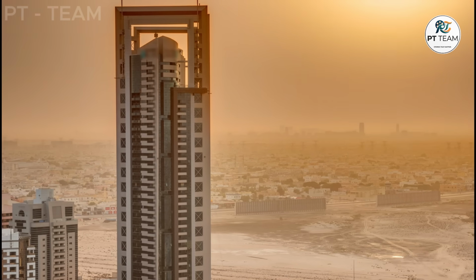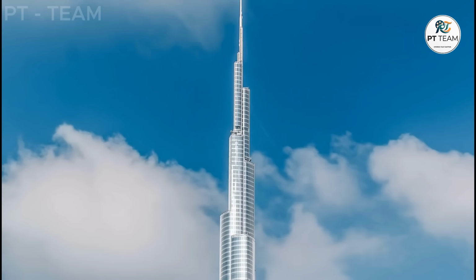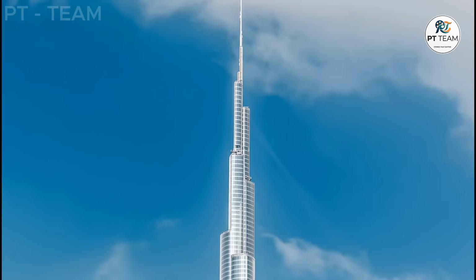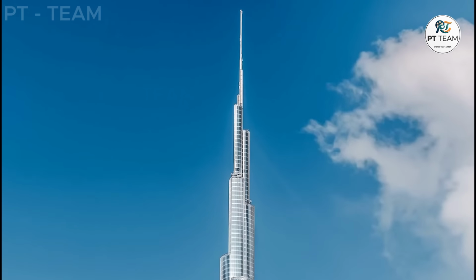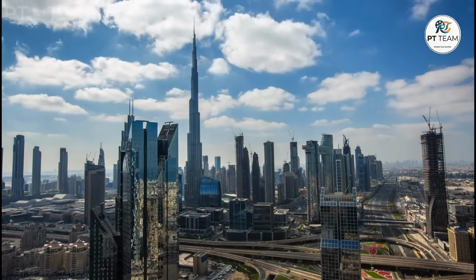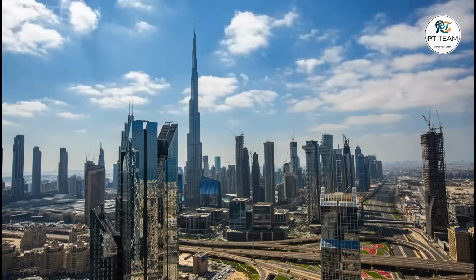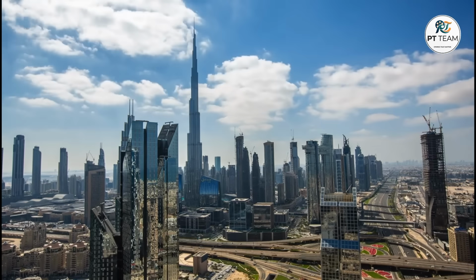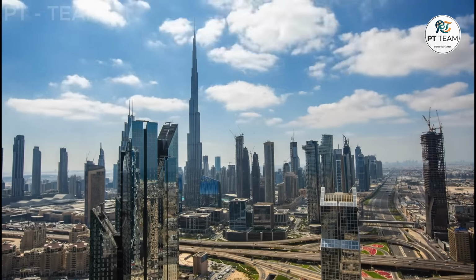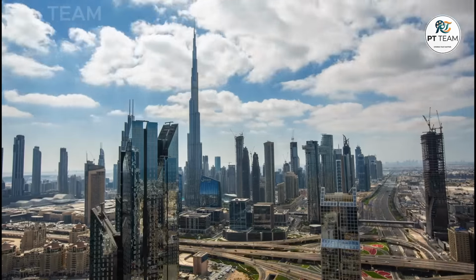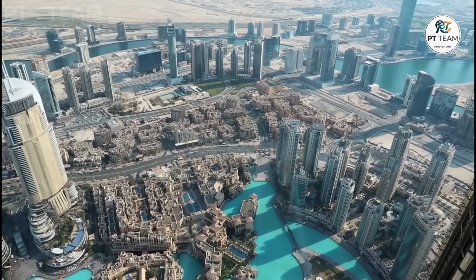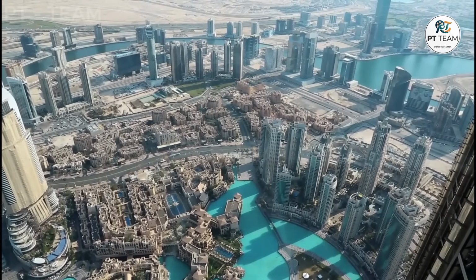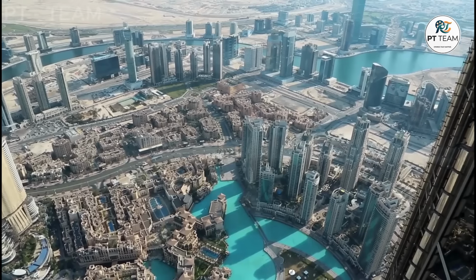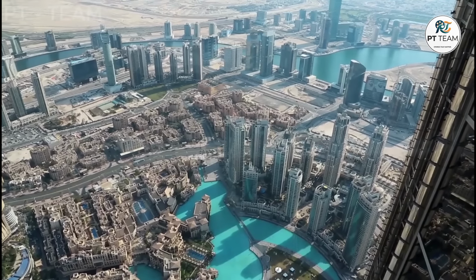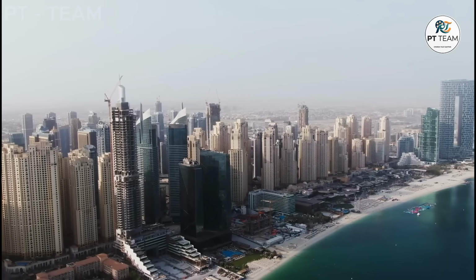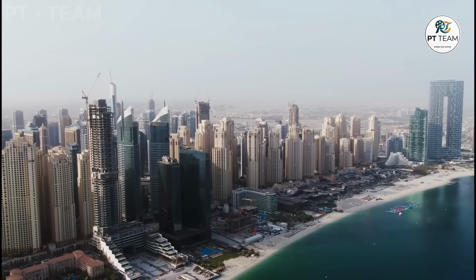But all of these technological advancements come with a strict conditional reality. Sensors do not physically replace clogged filters. Software cannot climb into a dark duct and repair a broken rubber seal. Data is entirely useless if the management team does not have the budget to deploy human labor to fix the problem. None of these innovations eliminate the fundamental need for continuous physical maintenance. Dubai can absolutely keep the desert outside its luxury towers, but it can only do so by aggressively pulling its air through machines that are never allowed to stop.